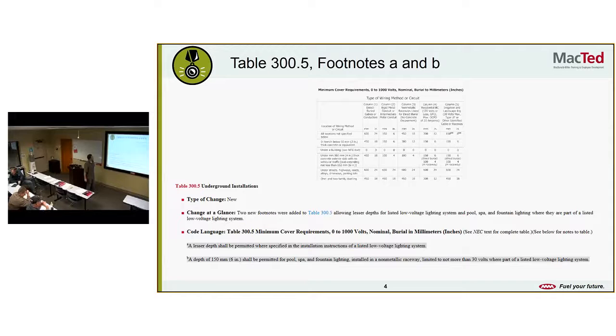So it looks like for the minimum cover requirement, 0 to 1,000 volts, what they've added is that a lesser depth shall be permitted where specified in the installation instructions of a listed low voltage lighting system. So if the instructions say that you can do it, you can do it. Because what they're concerned with here is the low voltage stuff, you're not going to hurt anything if you hit it with a shovel, it sounds like to me. Like all those little lighting systems you get at Home Depot. Exactly. Yeah, little low voltage transformer stuff. Exactly. So they've lowered that.